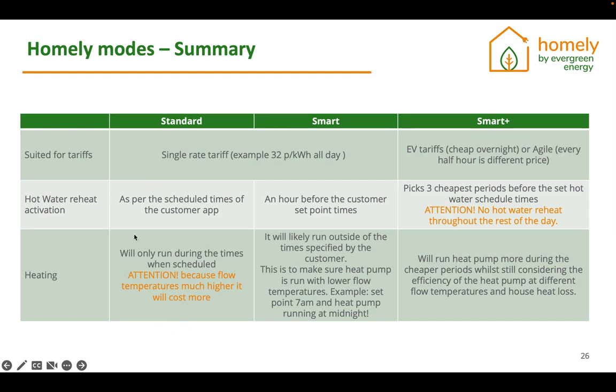In standard mode, you'll see that the hot water reheat is going to turn on as per the scheduled times, and the heating will only come on at the scheduled times. This will mean that the flow temperatures of the heat pump will be much higher than they would have been in smart mode, and they'll see the heat pump going flat out at the points when their set point goes below whatever they've set, especially at the beginning of those set points, because the house would have cooled down, let's say, before the morning set point. This will lead to higher flow temperatures, which will mean lower efficiencies, which will mean higher cost to the end customer.